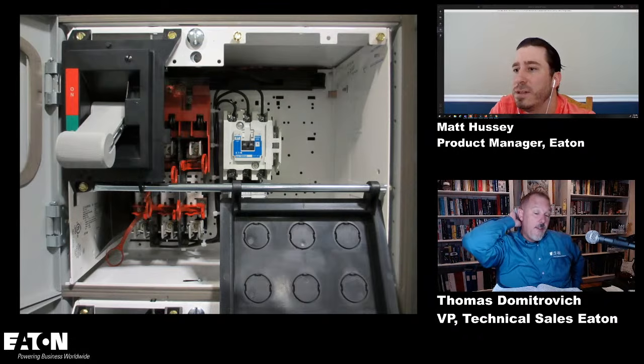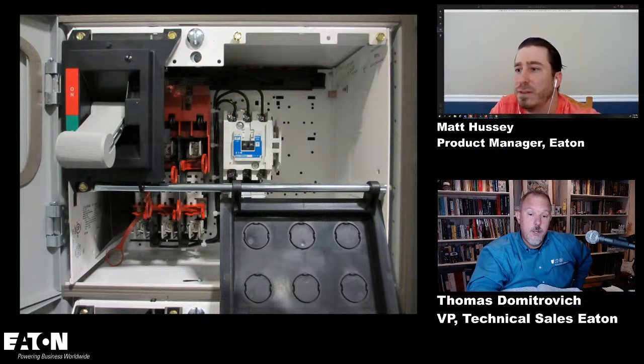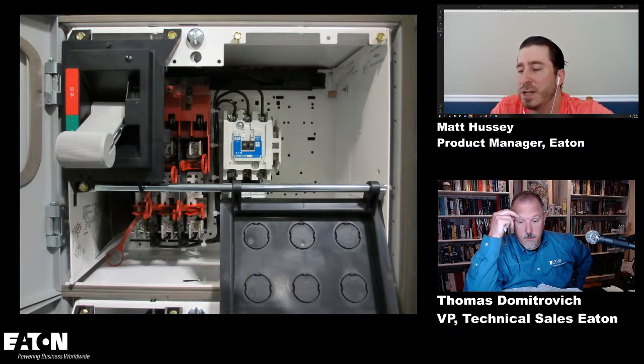Okay, so you as a manufacturer put these together. How do you test a bucket? What do you do to test that? You'd have to have a listed section as a sample, and that unit would be identified. You'd mark down all the different connections to the bus, and all the hardware that's included in there. It has to be tested, one, from a heat rise perspective, to make sure that we're not going to get too hot and melt insulation. And then we do a short circuit test. That door is normally closed, so you have to make sure that if there is a bolted fault, the equipment is able to withstand that event.